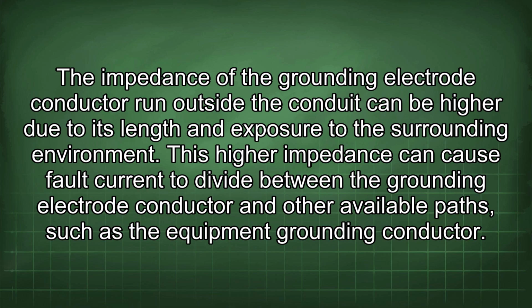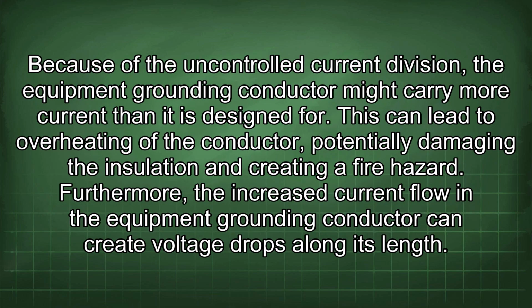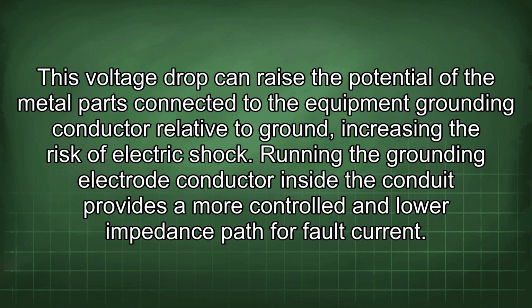This higher impedance can cause fault current to divide between the grounding electrode conductor and other available paths, such as the equipment grounding conductor. Because of the uncontrolled current division, the equipment grounding conductor might carry more current than it is designed for. This can lead to overheating of the conductor, potentially damaging the insulation and creating a fire hazard. Furthermore, the increased current flow in the equipment grounding conductor can create voltage drops along its length. This voltage drop can raise the potential of the metal parts connected to the equipment grounding conductor relative to ground, increasing the risk of electric shock.